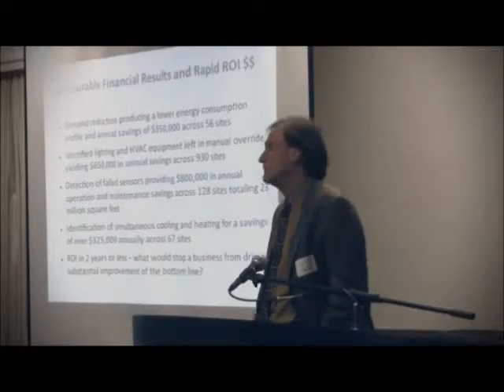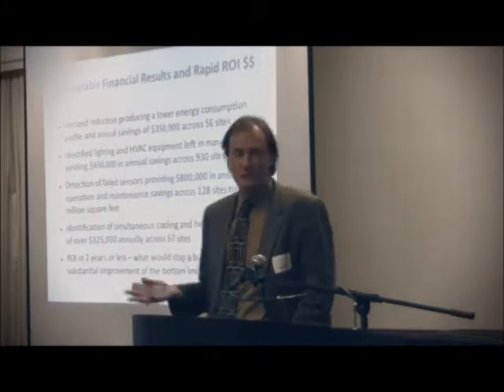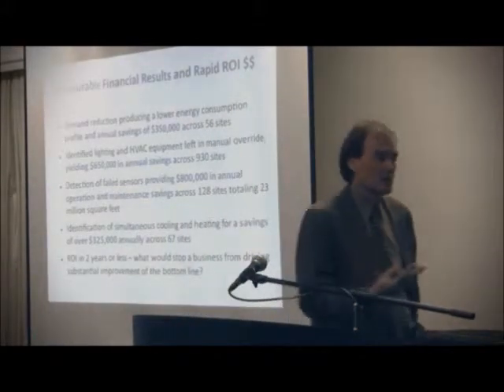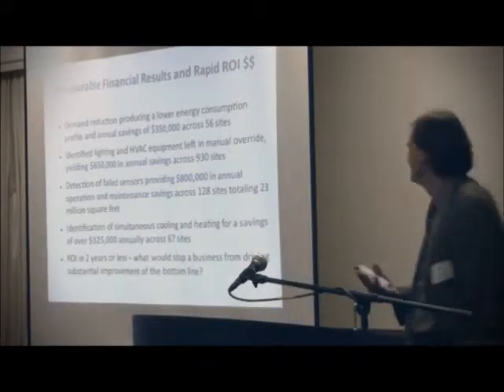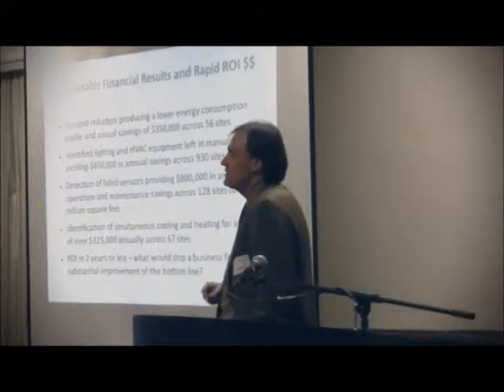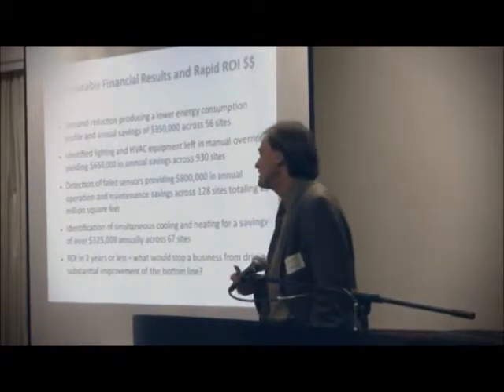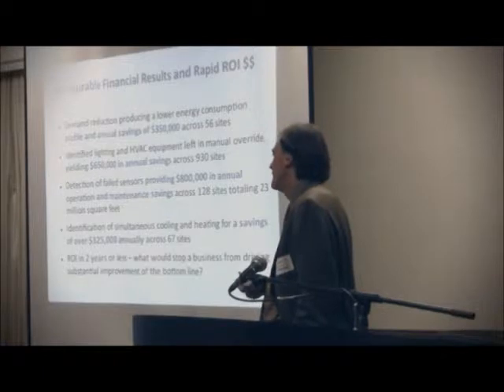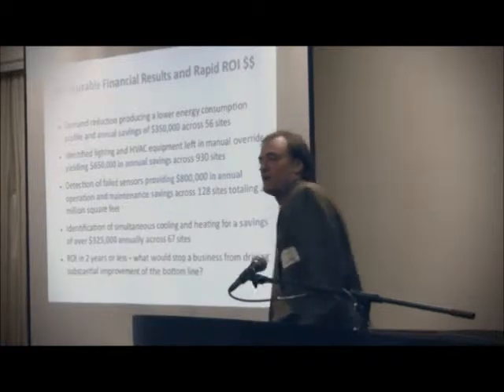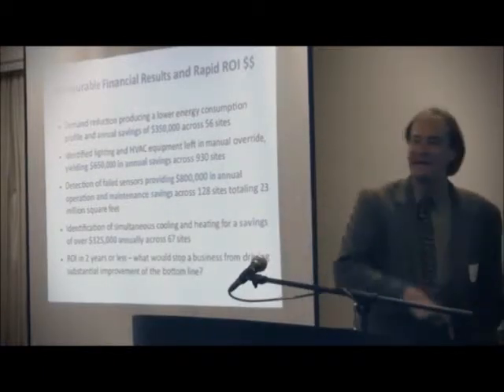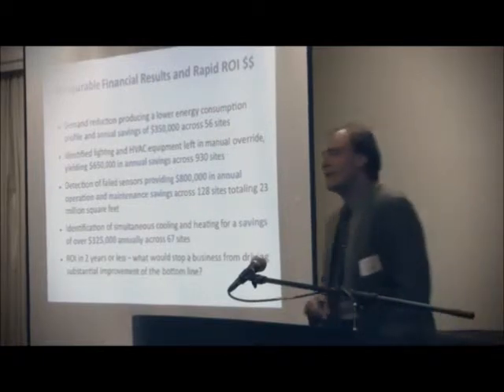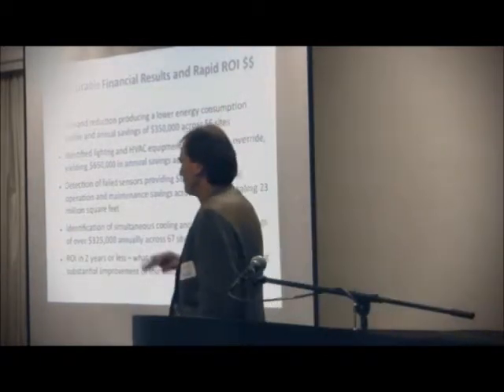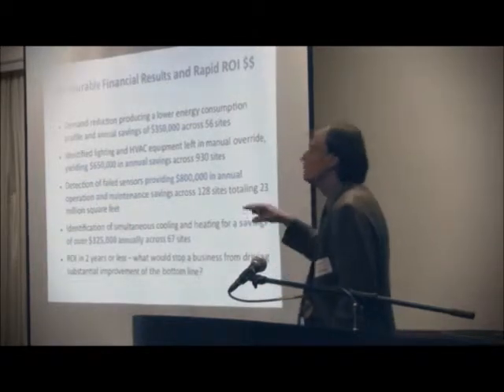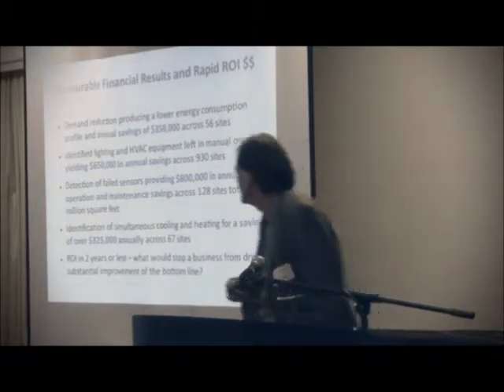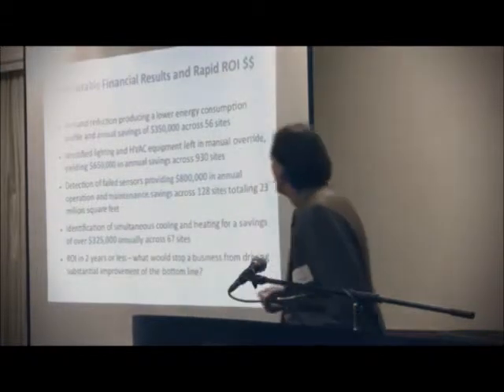Another one, manual override. I know everybody in this room runs their buildings better than that, but for some reason there are a lot of buildings out there where overrides get forgotten. Failed sensors, interesting surprise, how many bad sensors are out there. It's easy to detect the one that fails so the signal goes to some insane number. But sensors can fail in a reasonably acceptable range and cause systems to just not run right, continuing to heat and cool when they shouldn't be - simultaneous heating and cooling, etc.